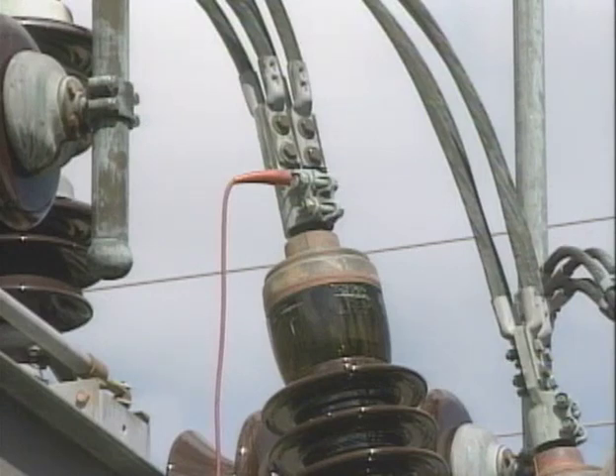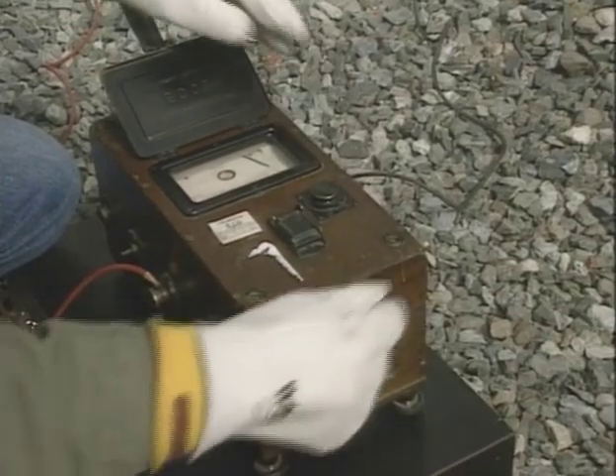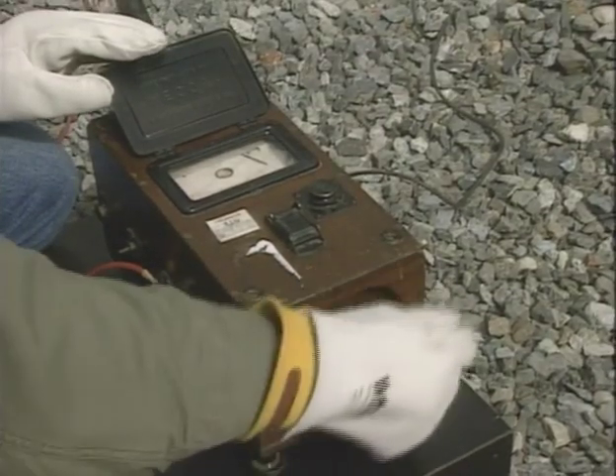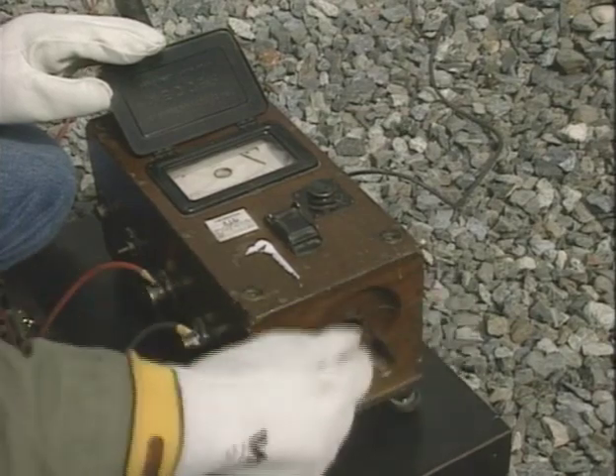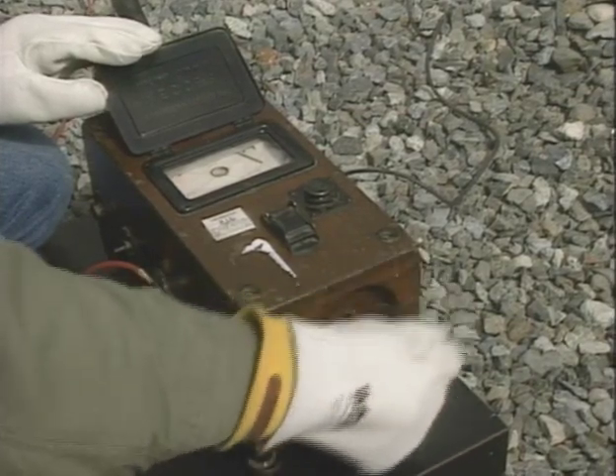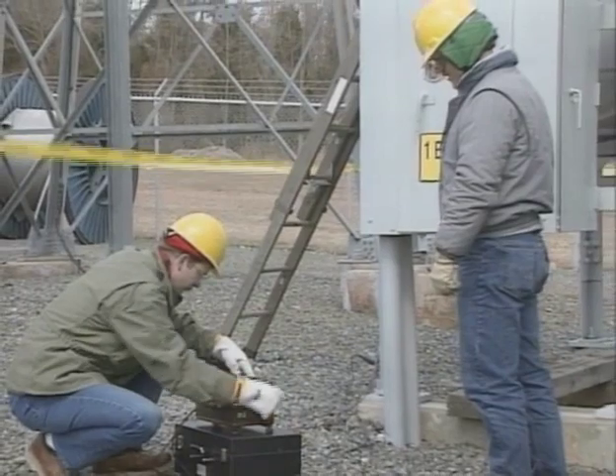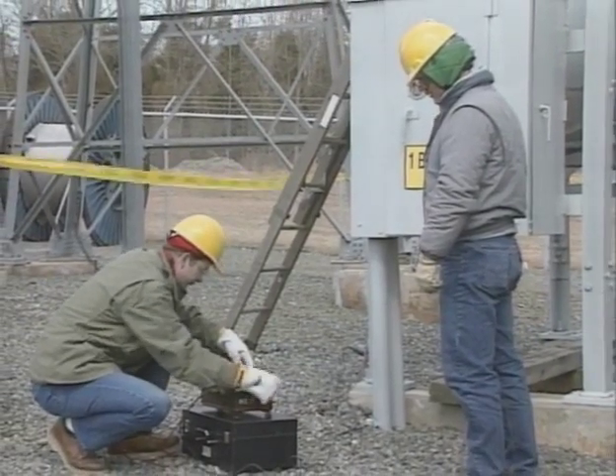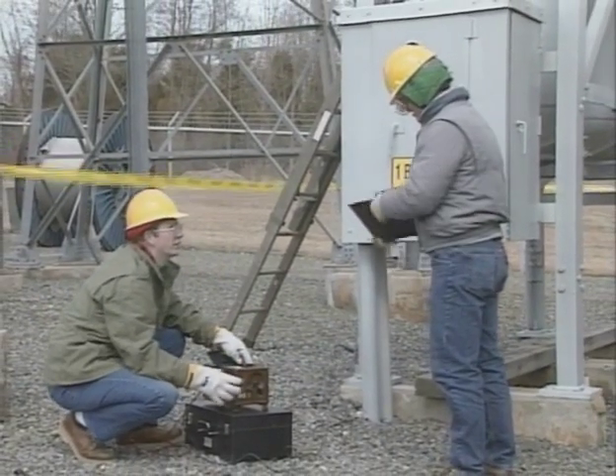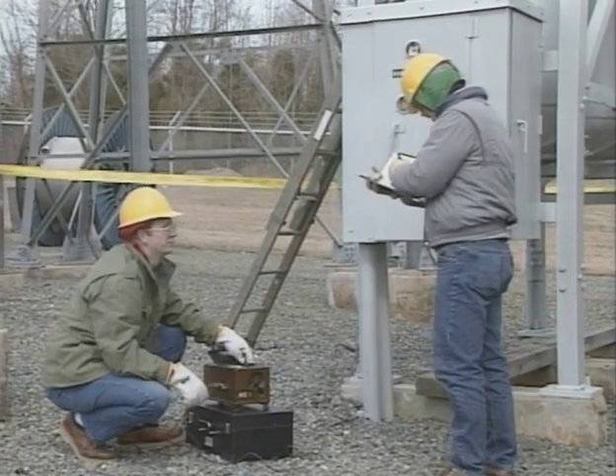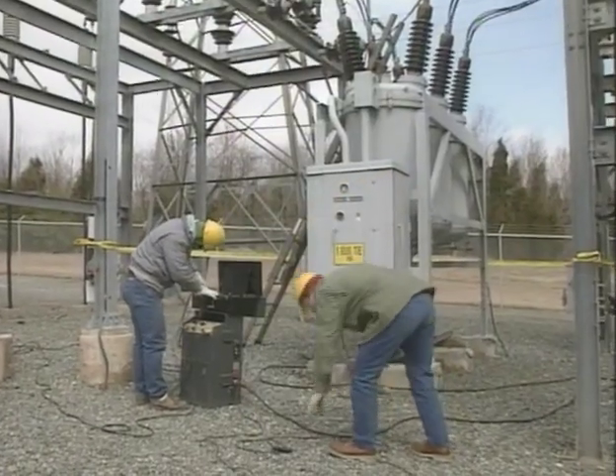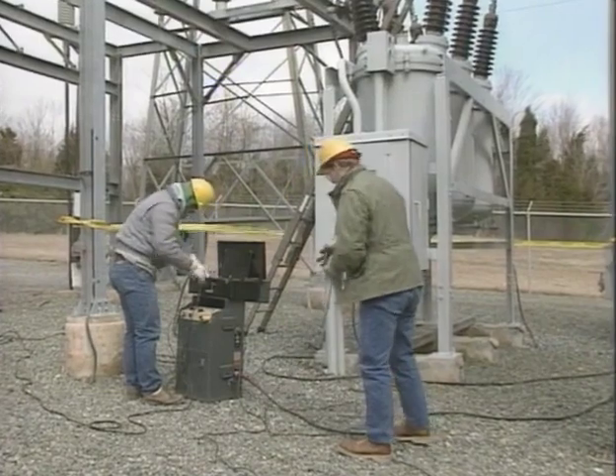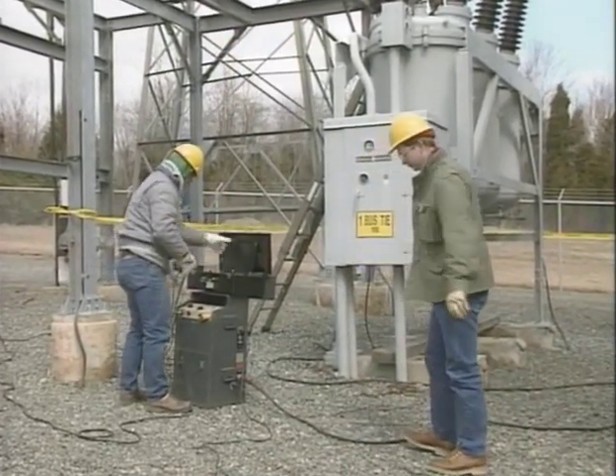Then, leakage current is measured either to ground or across the open contacts to the other bushing terminal. The test instrument uses the DC voltage and leakage current values to calculate and display the insulation resistance. If the insulation resistance is lower than an acceptable minimum, the cause of the low insulation resistance must be identified and corrected. A fourth proof test that may be performed on a circuit breaker is the power factor test.